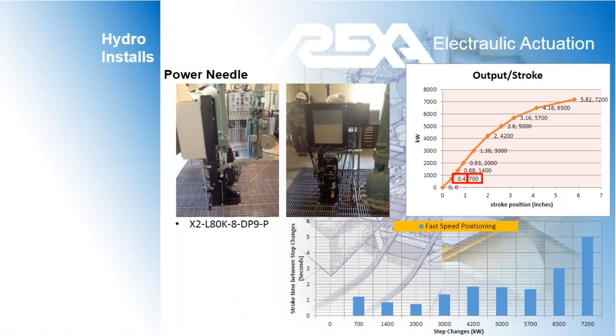Now, a power needle is a critical application for any impulse turbine design. Power needles can operate head ranges upwards of 2,000 meters, so roughly more than 6,000 feet. An added challenge is the ever-changing electricity demand, forcing plants to cycle more frequently. Under these conditions, REXA is well suited for reliable control of the power needle to regulate the flow of water. Now, the power needle is a great application for REXA. REXA can hold set point for long periods of time because it is hydraulically locked in place.